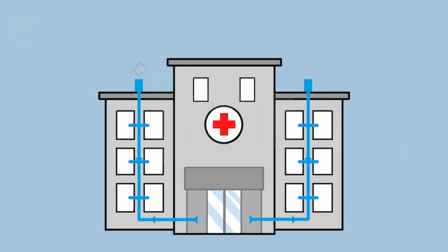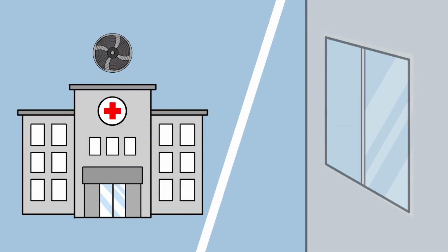A third factor to consider is where the air must be exhausted. The Code for Ventilation of Healthcare Facilities, ANSI/ASHRAE Standard 170, requires all air in new rooms to be exhausted directly to the outside. It is important to do everything possible to exhaust the air outside. This method has the fewest single points of failure, which ultimately best protects the staff and other people in the building from airborne germs.